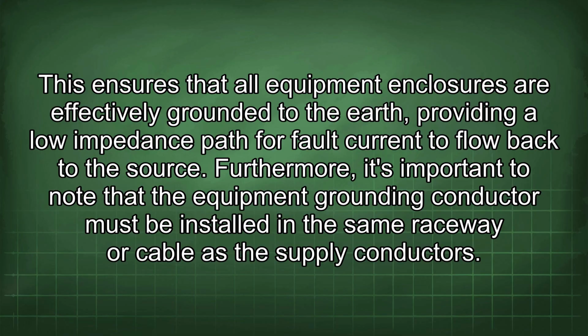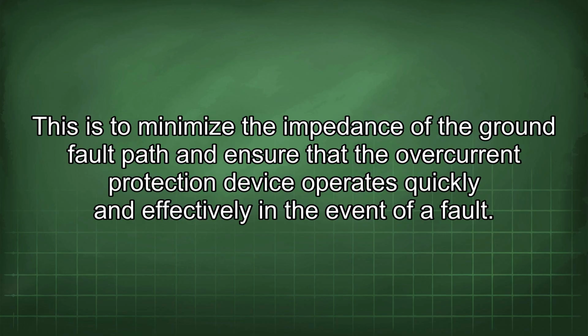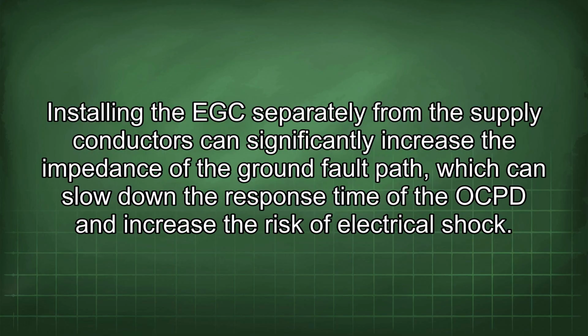Furthermore, it's important to note that the equipment grounding conductor must be installed in the same raceway or cable as the supply conductors. This is to minimize the impedance of the ground fault path and ensure that the overcurrent protection device operates quickly and effectively in the event of a fault. Installing the EGC separately from the supply conductors can significantly increase the impedance of the ground fault path, which can slow down the response time of the OCPD and increase the risk of electrical shock.